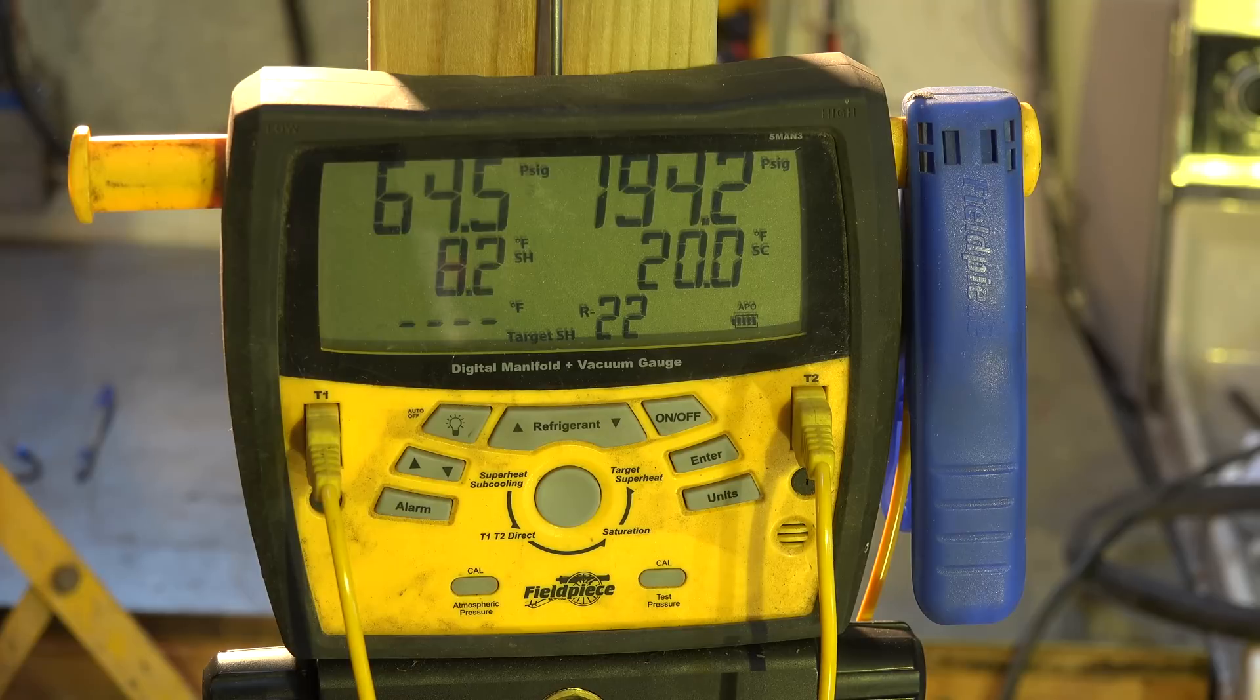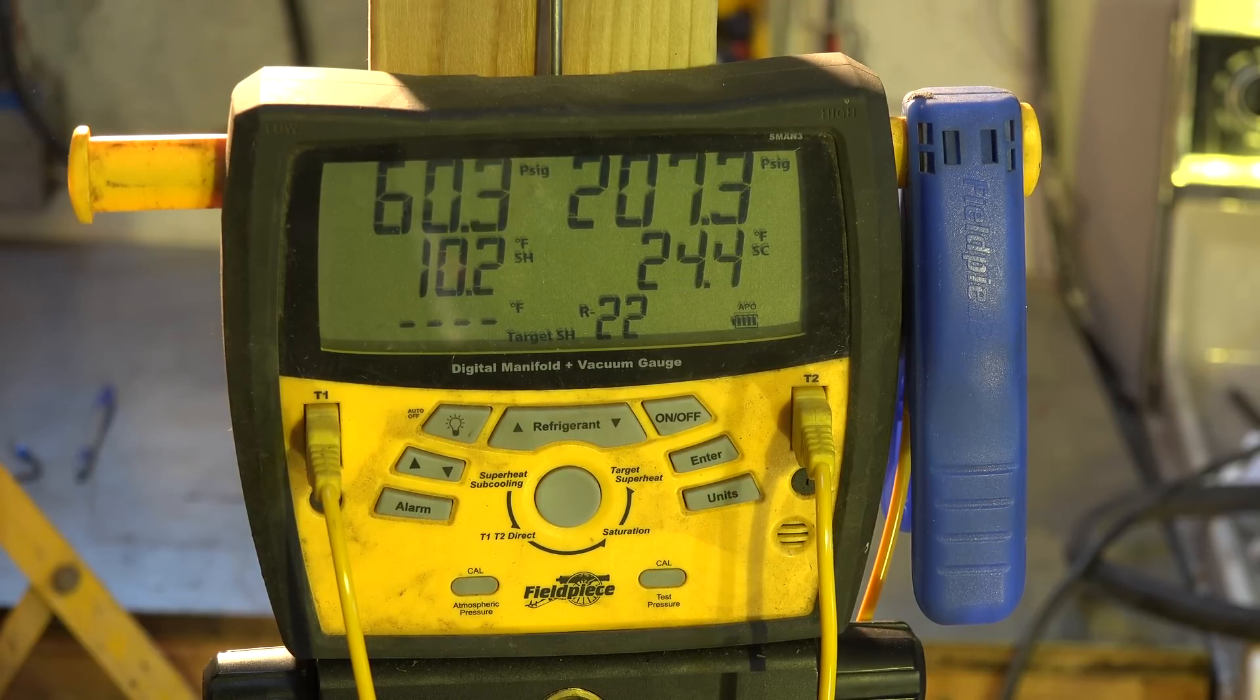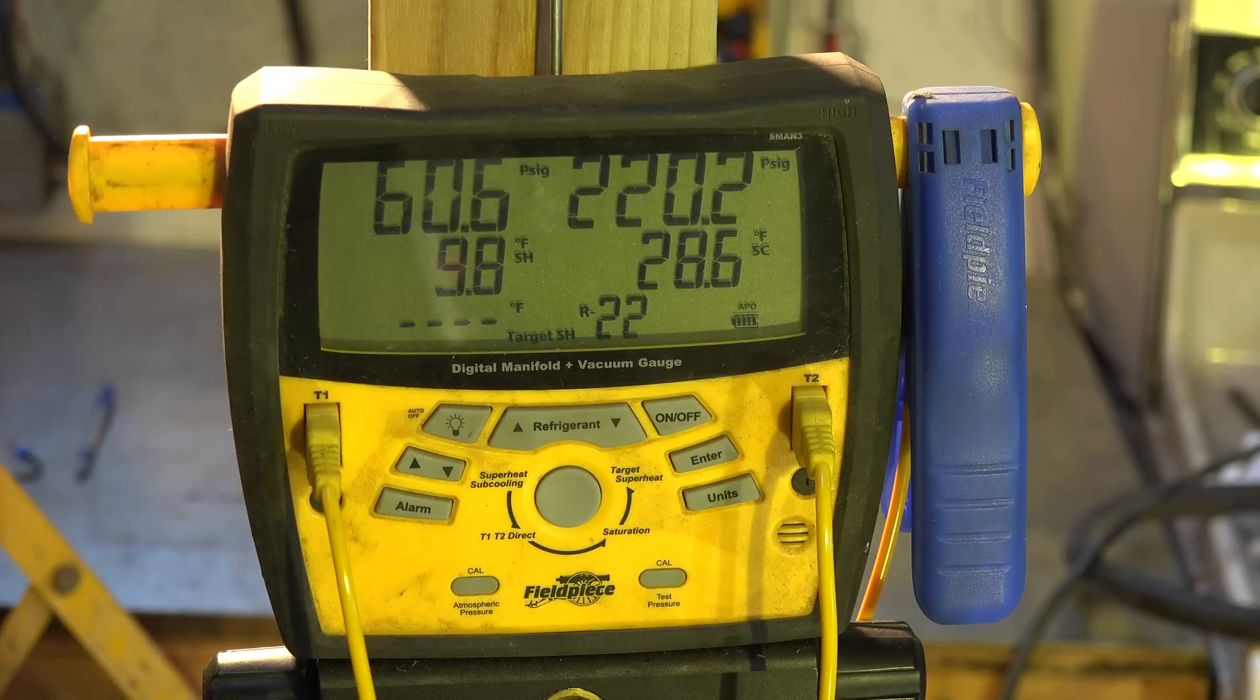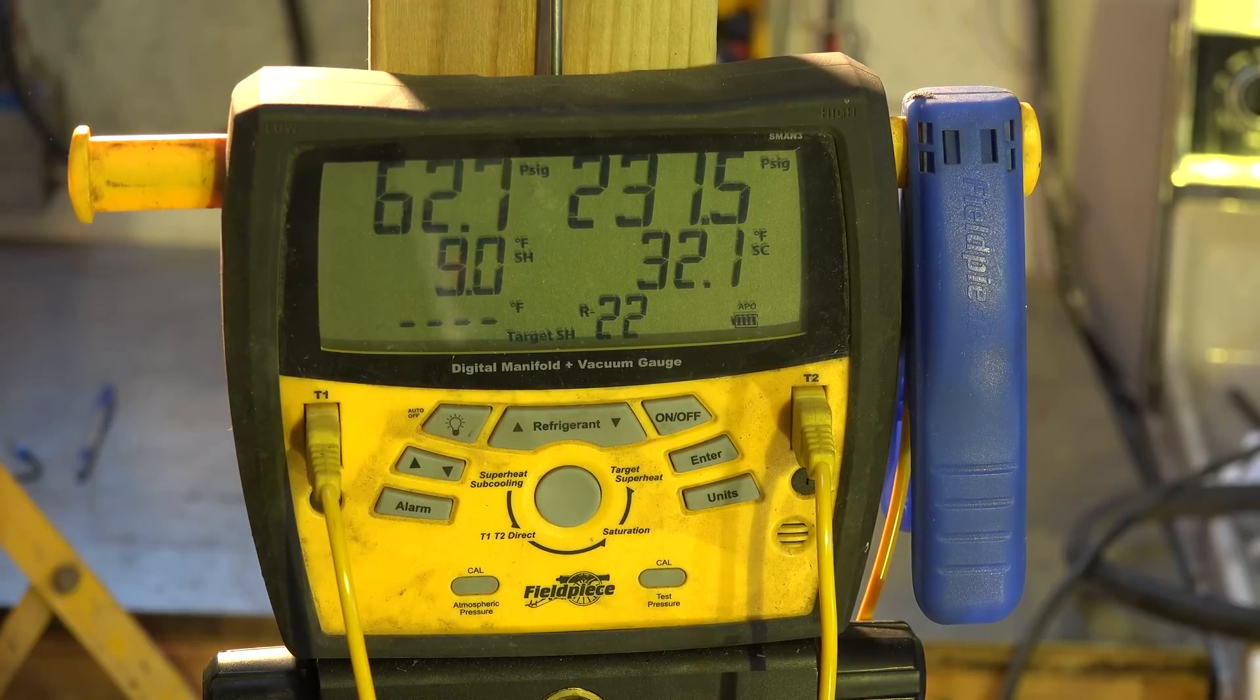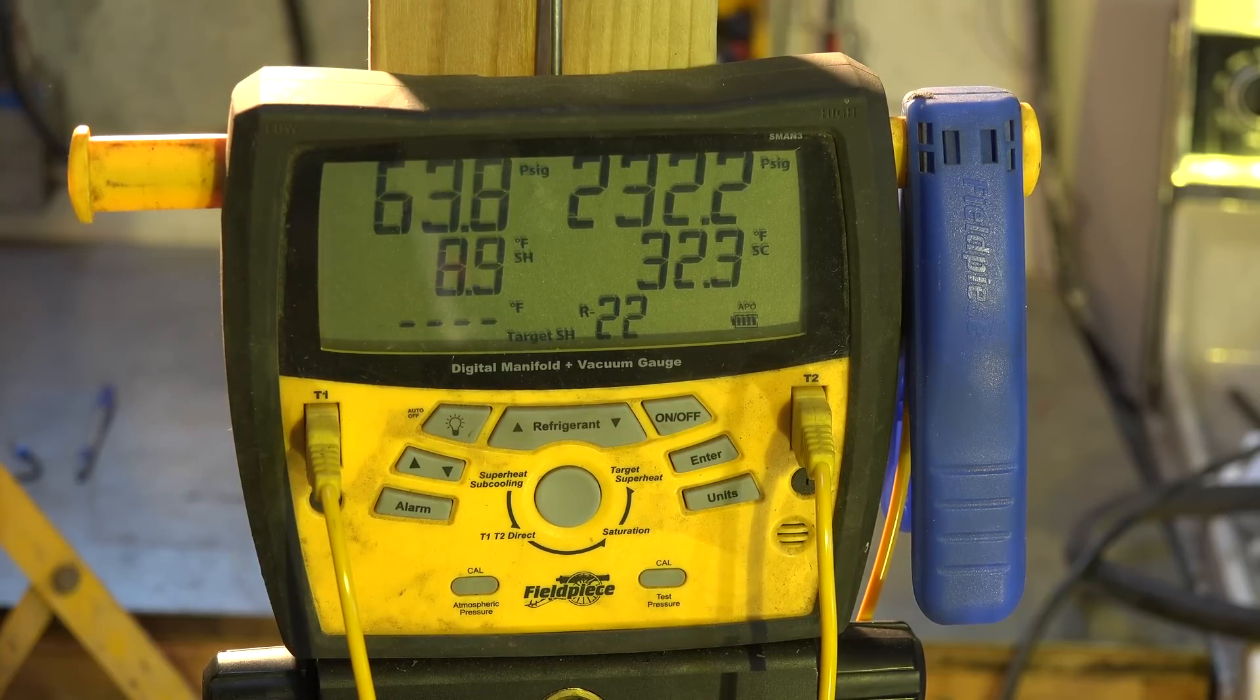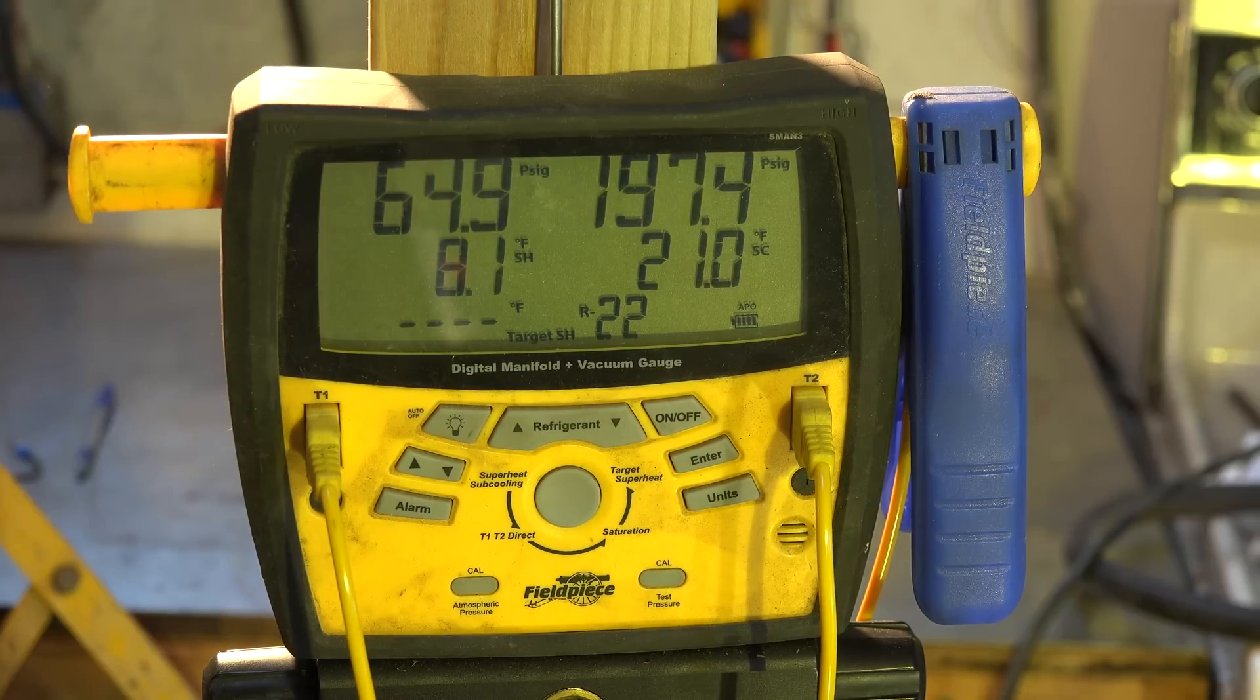Okay, I hope this makes sense. I don't think this is the best way to control head pressure because of that varying head pressure compared to suction pressure, especially when you use a fixed orifice device. But that's how a lot of these things are set up. There are a number of different head pressure controls that work far better, but this is fairly common because it's probably the cheapest one out there. Anyway, that's it on this one.